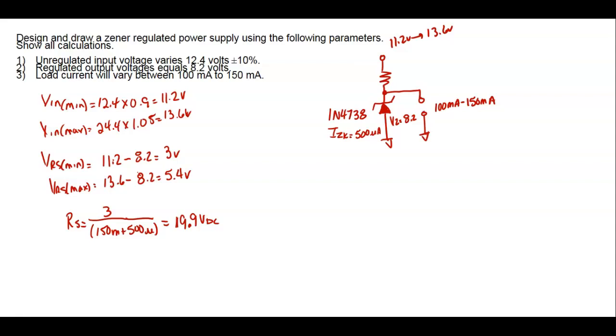We still can use 18, right? So, what I'm saying is that if it was like 8, that makes sense. So we'll come over here and we're going to take this and find the next standard size. We're still working on equal. So what's the standard size closest to this? Down from that. Okay. Always down, right? Then we're going to multiply this times 1.05, which gives us what? 18.9.